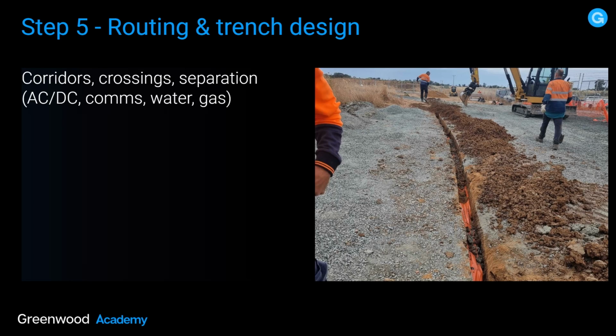At the end of the day, you cannot change the existing soil temperature and its thermal resistivity, so that may mean that you bring in engineered soil, or you go trenchless and you get those cables above the ground. You just have to do the proper analysis. Step 5, routing and trench design. So you have to take into consideration corridors, crossings, separation, AC/DC, comms, water, gas.